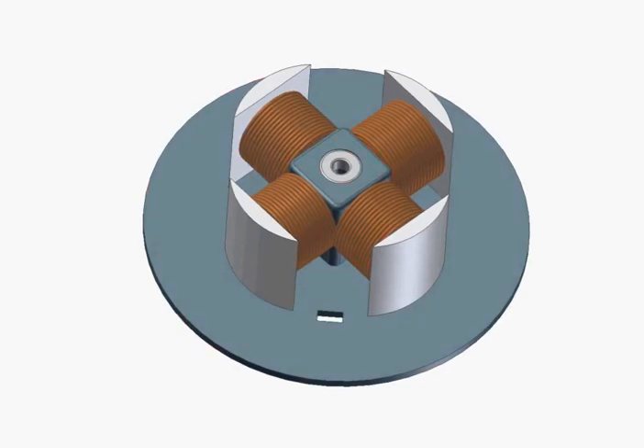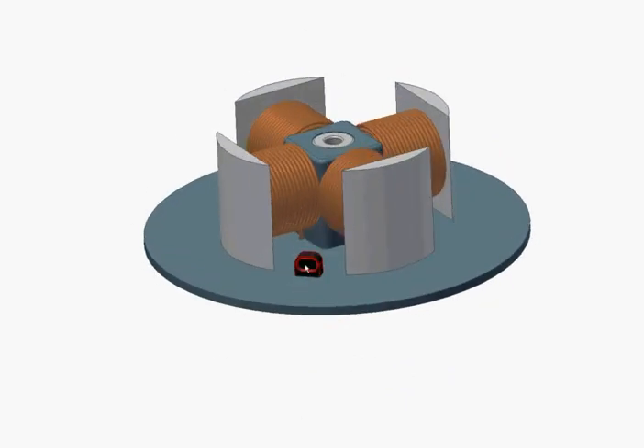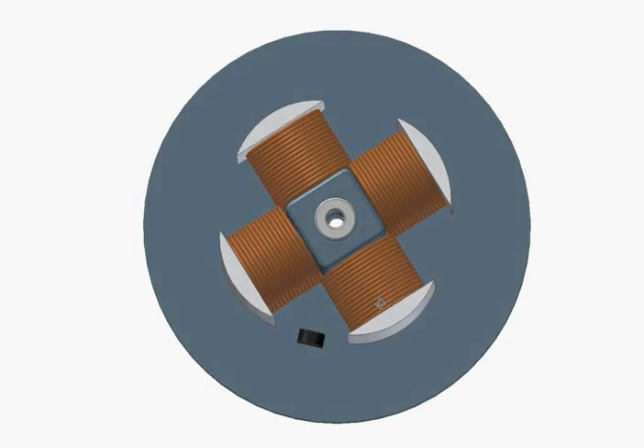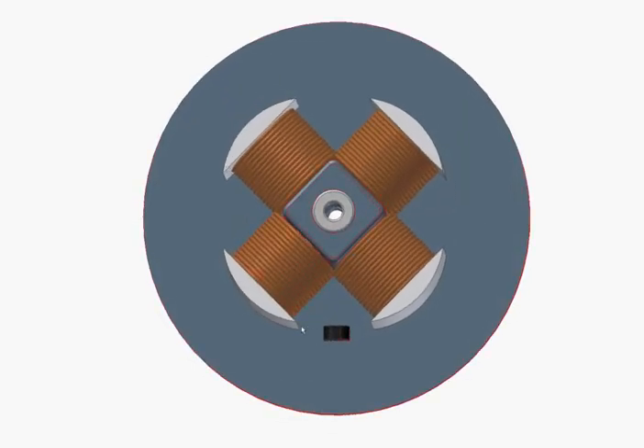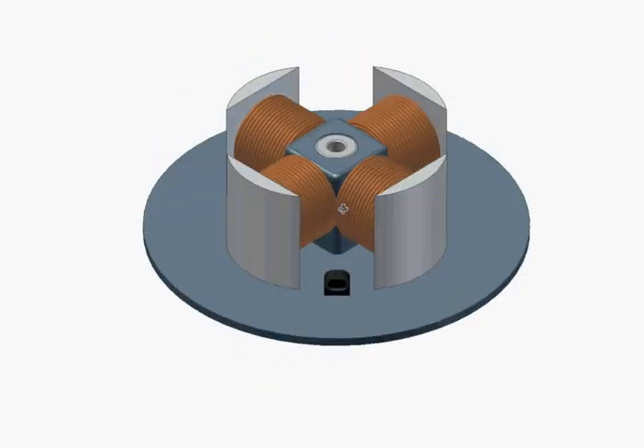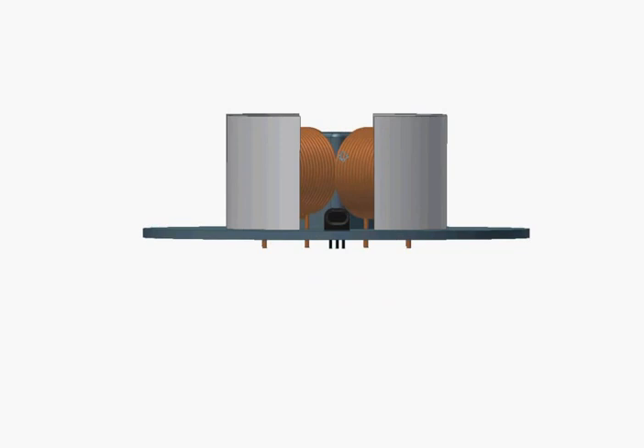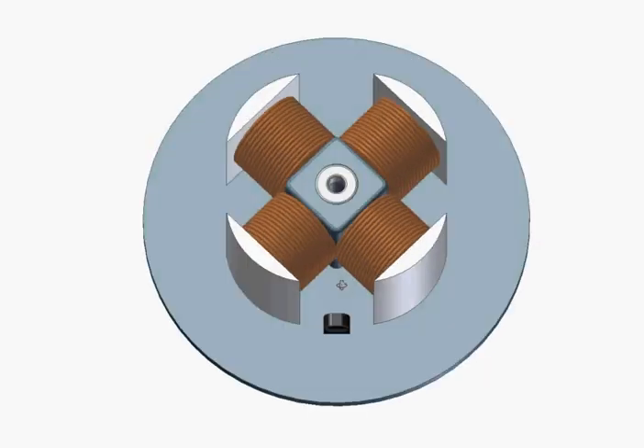Okay, now let's put the Hall sensor in position. It goes there. This is the Hall sensor. As you notice, it's between two armatures, and actually the geometric position of the Hall sensor is very critical. It must be exactly in the middle of the two armatures. Alright.